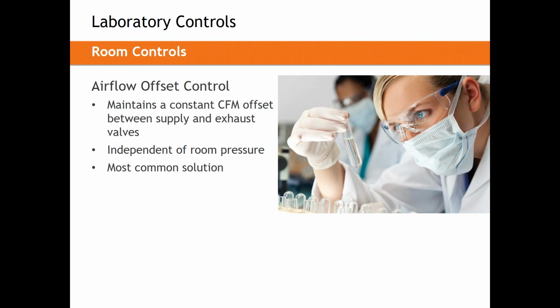We know that creates pressure, but we frankly have no idea how much pressure it will create. That will depend on the volume of the room and the leakage rate. In a more tightly sealed room, it will create more pressure. In a leaky room, less pressure. If we leave the doors open, or if we knock a wall down or punch a hole in the wall, it might actually create no pressure whatsoever. But the great thing, and also the downfall of offset control, is that it will not care about that whatsoever. It will maintain that 100 CFM of offset.